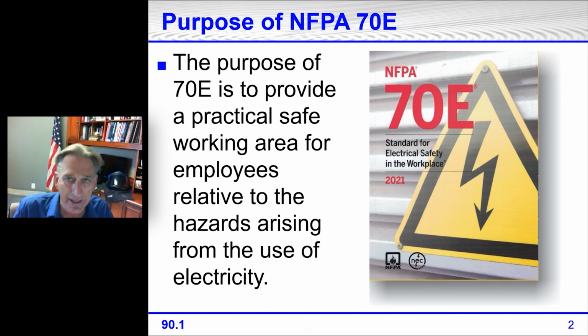All right, what we're covering today is the 2021 edition of NFPA 70E. NFPA 70E is electrical safety in the workplace. It's very similar to OSHA's electrical safety requirements. This document has been out for a number of years now. It is updated and revised every 3 years. This new 2021 edition just came out back in probably mid-September, and it is similar in the way that it looks and the way that it's revised to the National Electrical Code. The National Electrical Code is on a 3-year revision cycle and has been for a number of years, and 70E is now on a 3-year revision cycle, and it follows the year after the National Electrical Code.